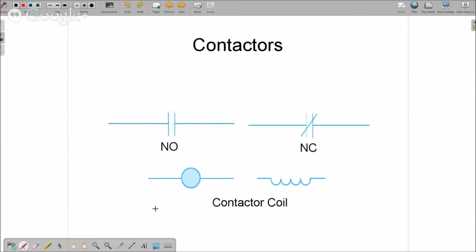There are two types of contacts on contactors: NO, which means normally open, and NC, which means normally closed. What that means is when there is no power applied to the contactor coil, this is the state that these contacts are in.